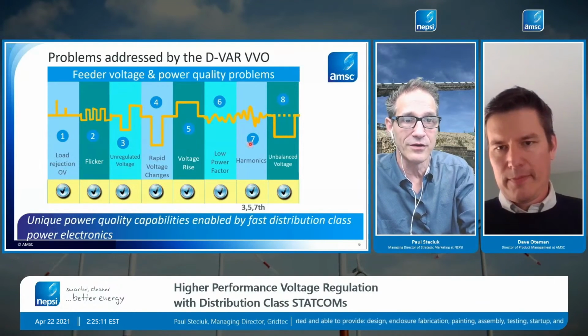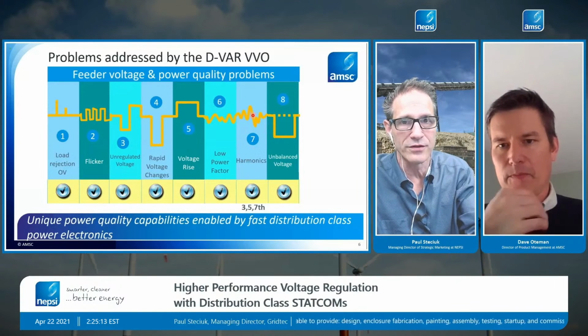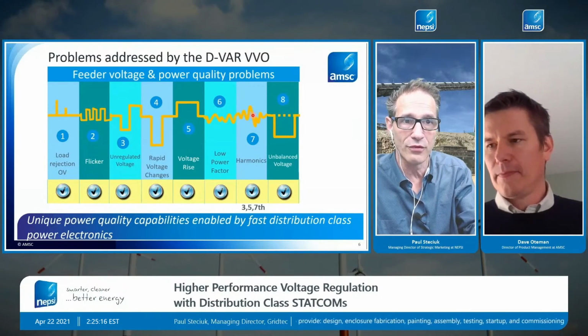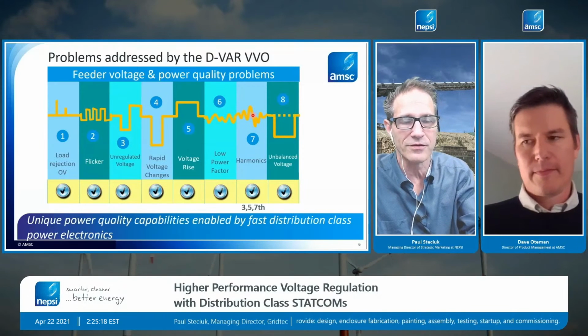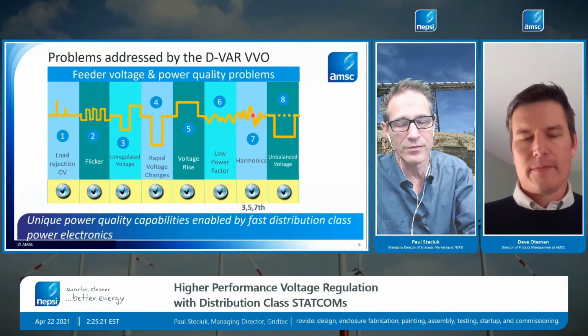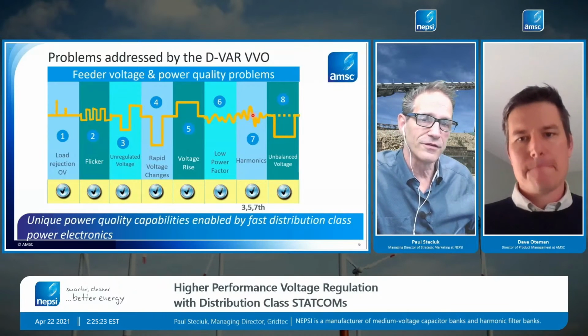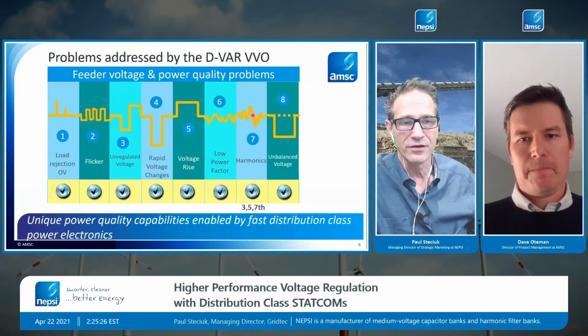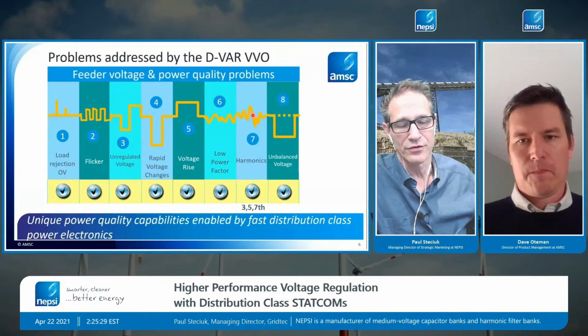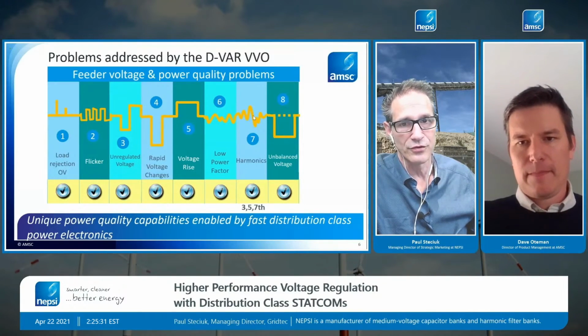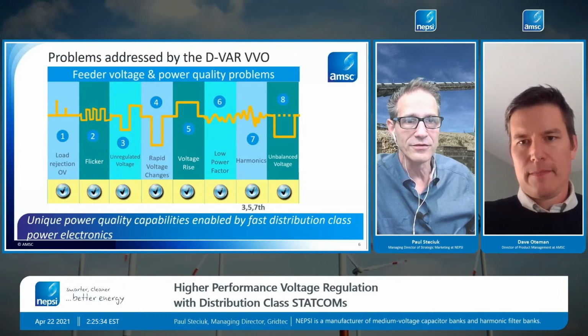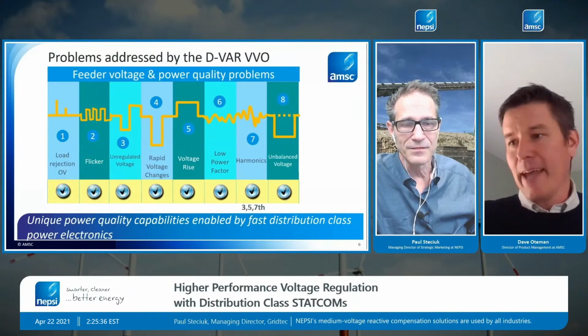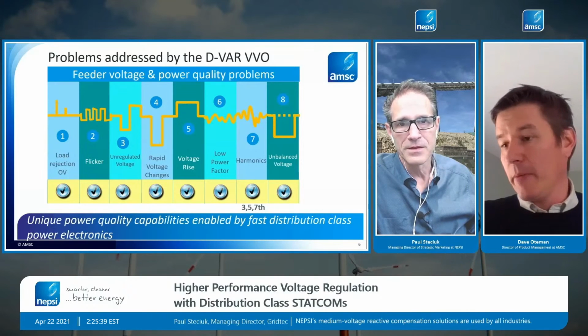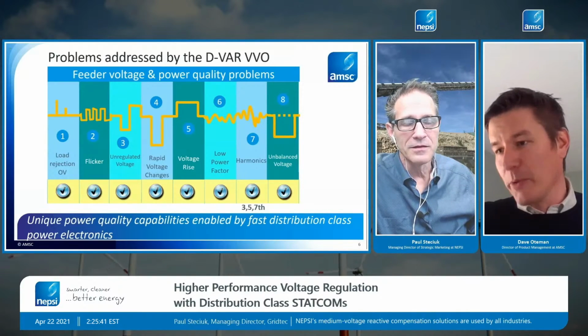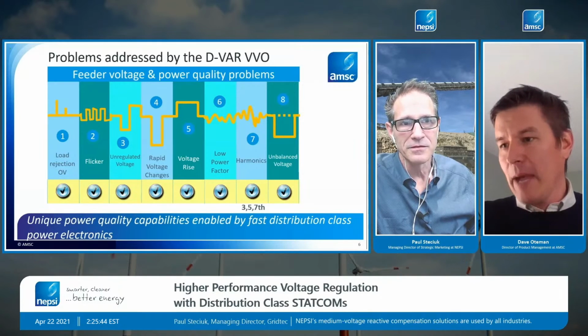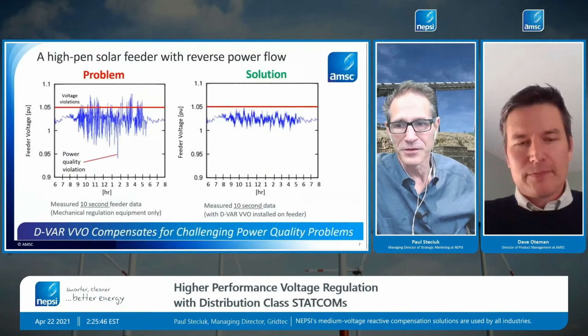We've talked about this phenomenon of resonance in other tech talks, and even in environments where the harmonic currents are really low, when you have resonance, you typically have a voltage distortion problem. So another benefit of this VVO product is it's less likely to cause resonance, which is less likely to result in high voltage distortion, a major power quality concern. And that's accurate. Yep. And the STATCOM actually does not look like an impedance. We'll talk more about that in the application section too.